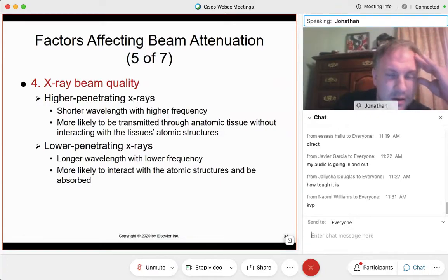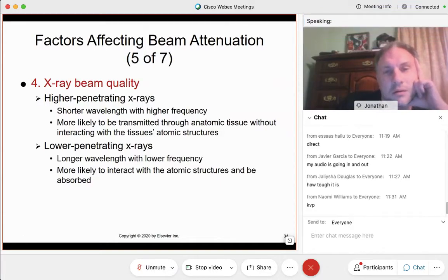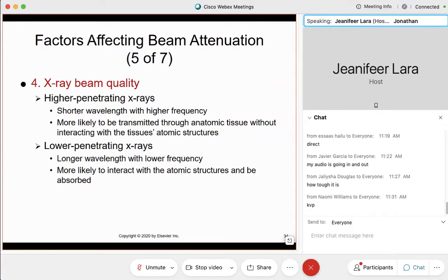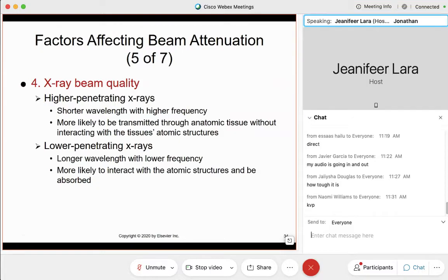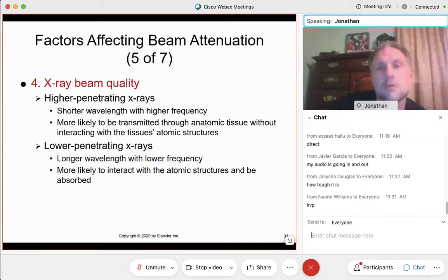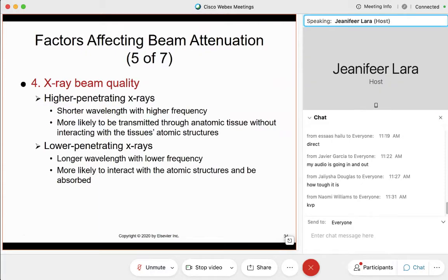I'm assuming. Yep. So what people use is AEC. AEC is going to be regulated by sensors, not in the image receptor, but on the actual Bucky itself. So the AEC is a sensor on the Bucky that terminates the exposure when it has received the right amount of energy, for differential absorption.